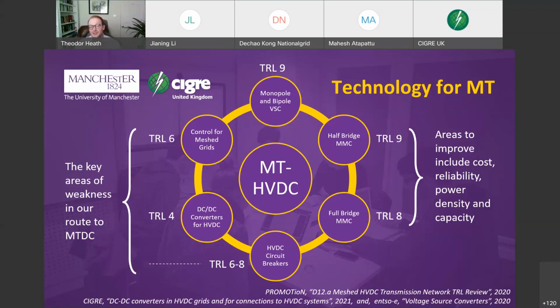Then we can look at HVDC circuit breakers, and there's a range given for these because there are different types at the moment: TRL 6 for the voltage assisted resonance converter, or VARC HVDC circuit breaker, TRL 7 for the hybrid HVDC circuit breaker, and TRL 6 for the active current injection circuit breaker. It says up to TRL 8 because we think we're going to be learning some lessons from the Zhangbei 4-terminal HVDC link, which is live testing these advanced HVDC circuit breaker prototypes at the moment.